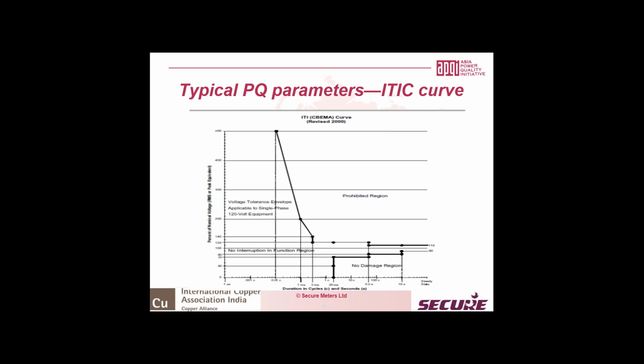And if you look at this curve, it talks about a prohibited region, a no damage region, and a no interruption in function region. The normal information technology equipment will withstand any event in the no interruption in function region, where the duration of the event is much smaller, even though the magnitude appears to be very high. And similarly, in the no damage region, the normal functionality of the equipment, typically a computer or a server, may get impacted, but there will be no damage to the equipment.